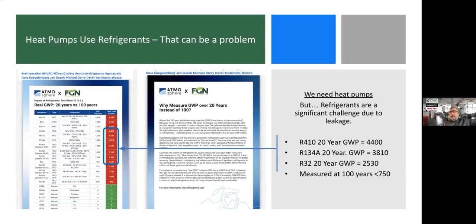However, refrigerants are all different, and the way we look at them is not a straight linear relationship. When we look at a refrigerant like R32 that shows great promise, we see that at a 100-year scale, the reported global warming potential is in the 750 range. Yet when we look at the actual lifespan of the refrigerant, if it leaks out of the equipment and into the atmosphere, it really dissipates and breaks down more on a 20-year scale. So when we start looking at the lifespan of the refrigerant in the atmosphere in a leak situation on a 20-year scale, the global warming potential pops back up to a very high number.